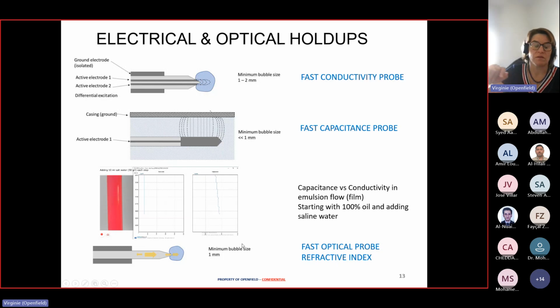Another type of probe that is very much deployed, the optical probe, especially if you have gas. So the optical probe is based on measuring the apparent refractive index of light. There are two fiber optics in the sapphire probe. One is shooting light toward the end of the probe, and depending on the fluid that is in contact with the sapphire probe, there will be a certain angle of reflection inside the probe. If there is gas or air, most of the light is reflected inside the probe and measured by the photoelectric detector. If you have oil, a substantial part of the light is going to leave the probe. This is how we can distinguish liquid from gas. And actually in good condition, we can also tell the difference between water and oil.